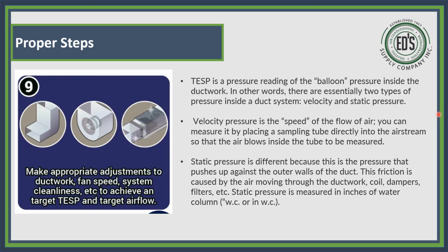What 0.10 does is that our ductwork metal and our transitions are all set up on the 1.0 system. So let's say a 2-ton has 800 CFM. Well, if you look at your ductulator on 1.0 velocity and see what 800 comes down to be, it's going to either be a 12 or a 14 or whatever. 14 carries 1,000 CFMs. That's for your 2.5-ton systems. And then you have your 16s, your 18s, and your 20s. And when you look at those numbers on the 0.1 of the ductulator, you're going to see I can get my 2 tons, my 2.5, my 3, my 3.5, and my 4 and 5 tons spaced out that way.